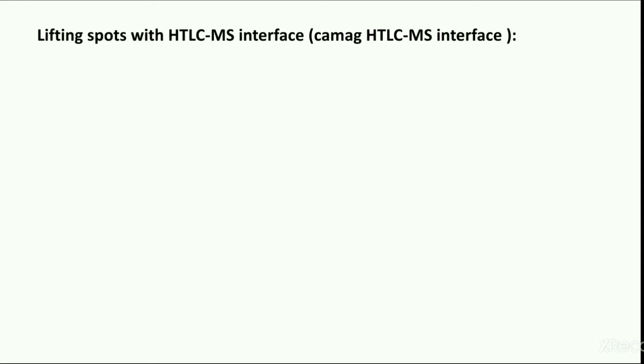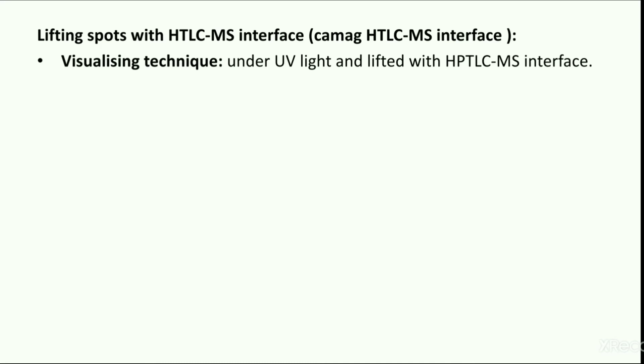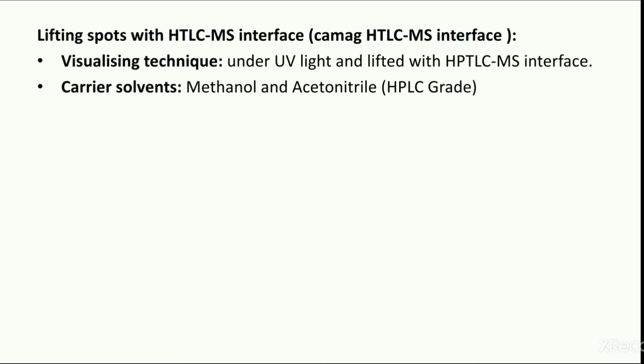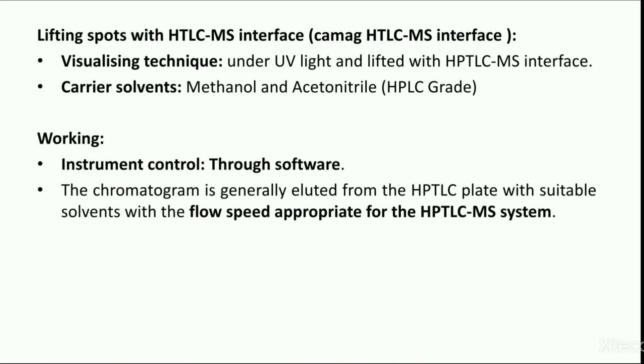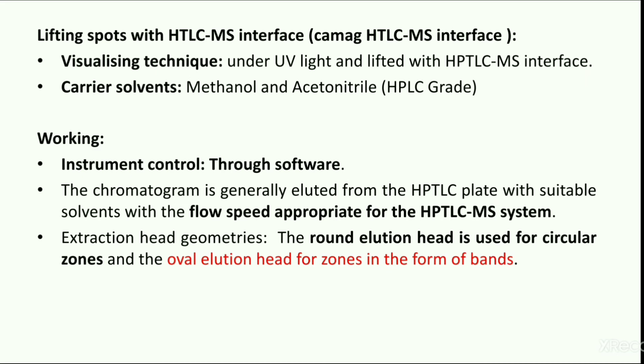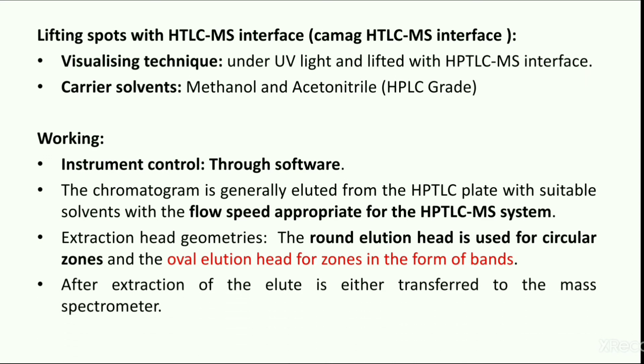Spots can be marked after visualizing under UV light and lifted with the HPTLC-mass interface. Solvents such as methanol and acetonitrile can be used for elution. Sample is applied on HPTLC plates and separated using suitable solvents. The developed chromatogram is generally eluted from the HPTLC plate with suitable solvents at a flow speed appropriate for the HPTLC-mass system. Additional extraction head geometries are available: the round elution head is used for circular zones, and the oval elution head for zones in the form of bands.